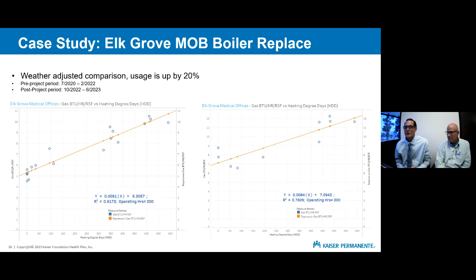If you think about it, you have a 1990s boiler in place, chugging along burning natural gas as well as it can, and then you put in a brand new 2020 boiler in its place, and it starts burning natural gas really, really well. So we do see energy use go up. The efficiency doesn't seem to matter much—the fact that it's a 97% efficient boiler on the nameplate or in the product catalog, we often don't see that come into play at all.